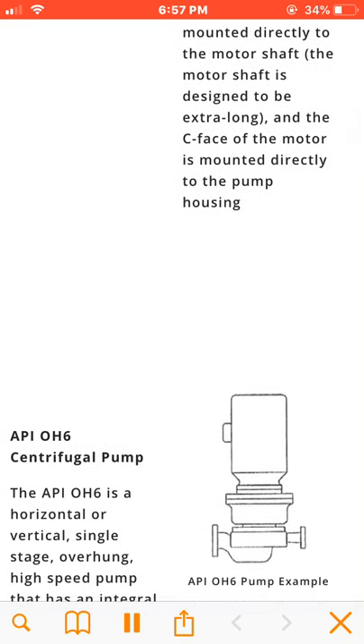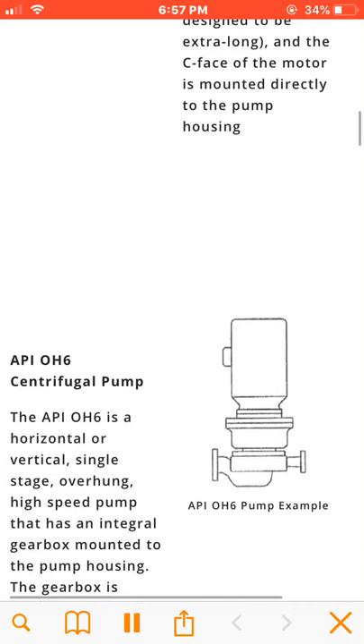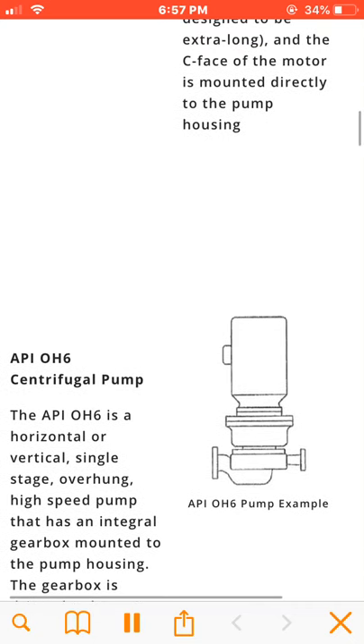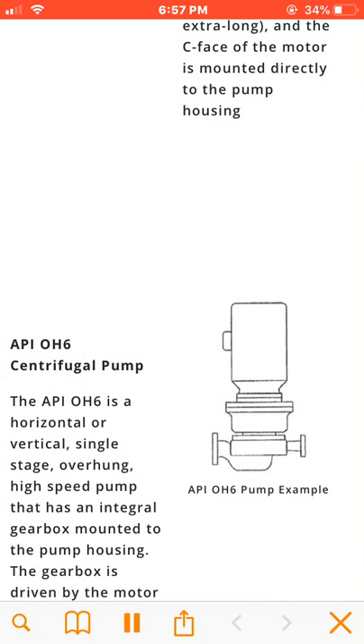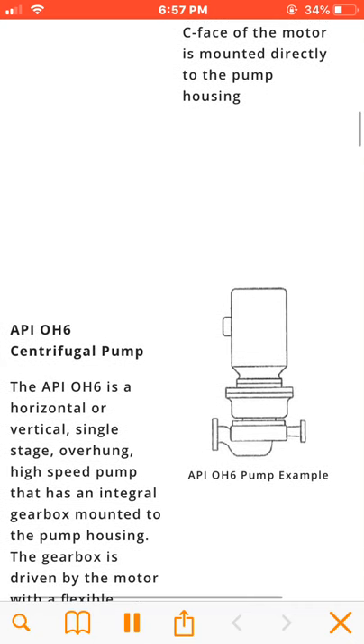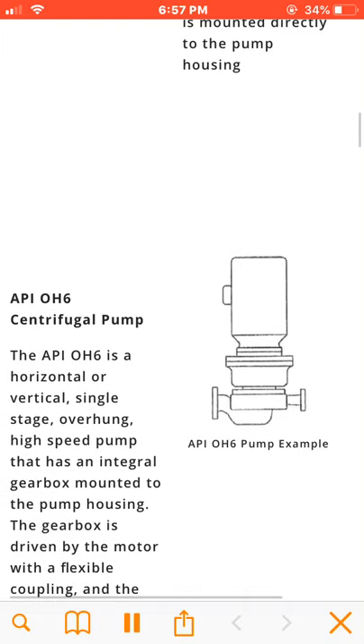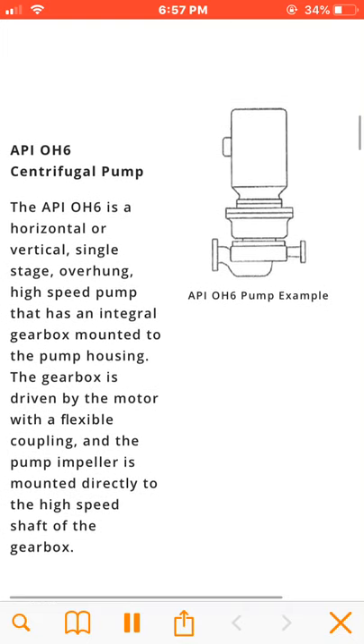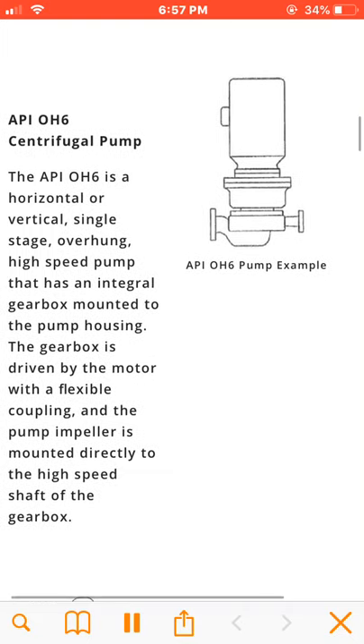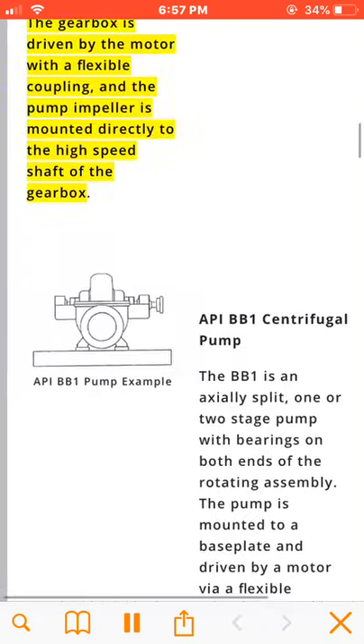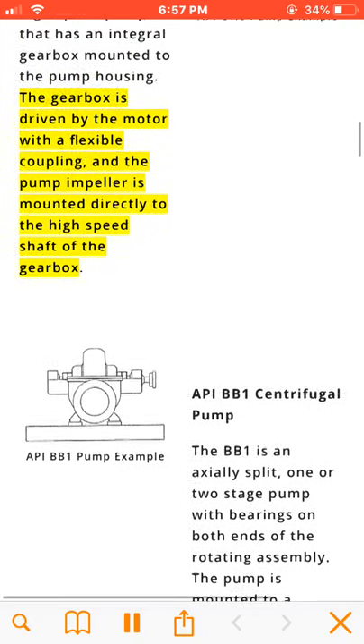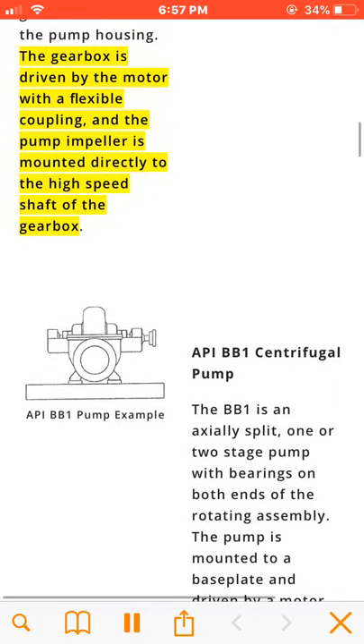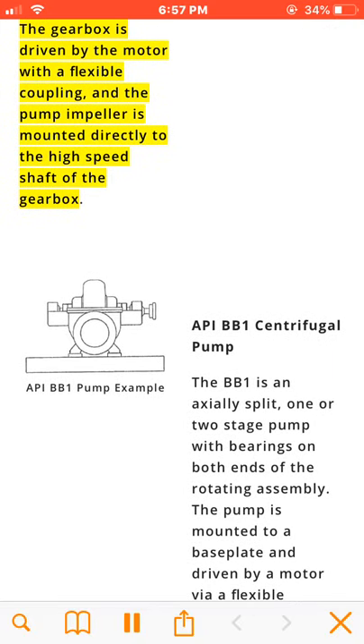The API OH6 is a horizontal or vertical, single-stage, overhung, high-speed pump that has an integral gearbox mounted to the pump housing. The gearbox is driven by the motor with a flexible coupling, and the pump impeller is mounted directly to the high-speed shaft of the gearbox.